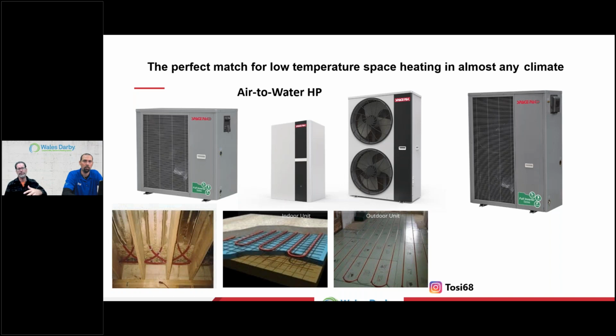Now I need to rebuild that storage back up, so I'm going to have a longer runtime. My steady state of efficiency will be achieved, instead of short cycling, that turn on, turn off. So yeah, if you have the space, as Rick was saying, it's cheaper to store than to produce BTUs.